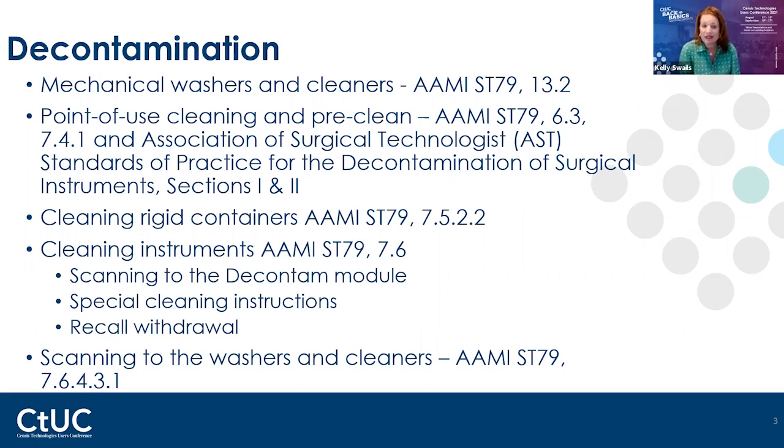Next on here, scanning to your washers and cleaners. So I hear, you know, we only have one ultrasonic, we only have one washer. Why do we need to document which one we send it to when we only have one? It's not so much which one I'm sending it to, as it is, think about your sterilizers. So we have no problem creating a sterilizer load. When that finishes, looking at the tape, making sure my parameters were met, 270, 10, 45. I verify everything's correct. I go into CensiTrac, I document that pass-fail, the cycle, document my biological, all that information.